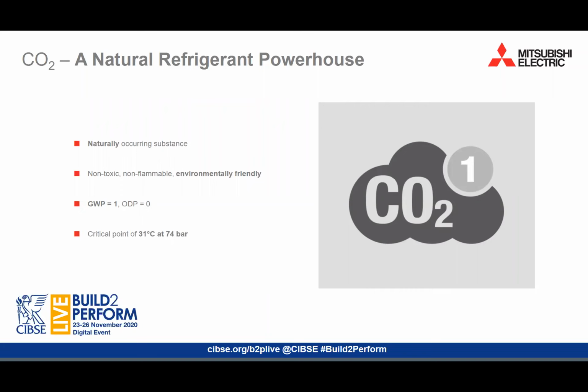CO2 is a naturally occurring substance that is non-toxic, non-flammable, and environmentally friendly, with a global warming potential of 1 and an ozone depletion potential of 0. CO2 also has a low critical point of only 31 degrees at approximately 74 bar.